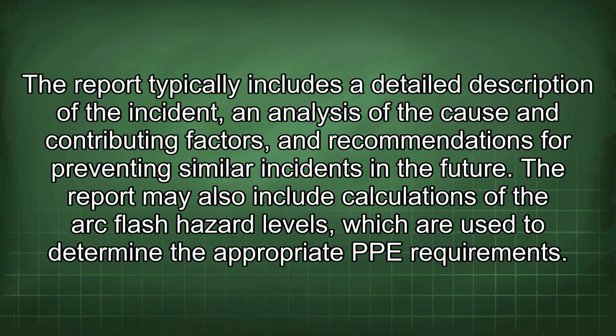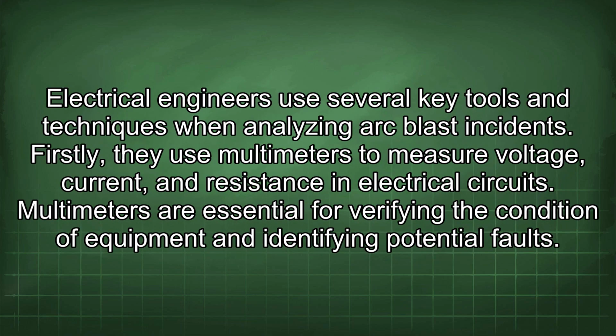The report typically includes a detailed description of the incident, an analysis of the cause and contributing factors, and recommendations for preventing similar incidents in the future. The report may also include calculations of the arc flash hazard levels, which are used to determine the appropriate PPE requirements. Electrical engineers use several key tools and techniques when analyzing arc blast incidents.